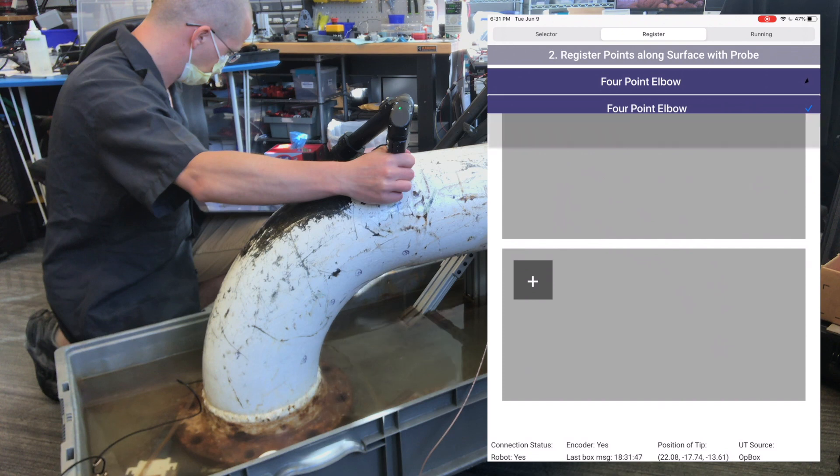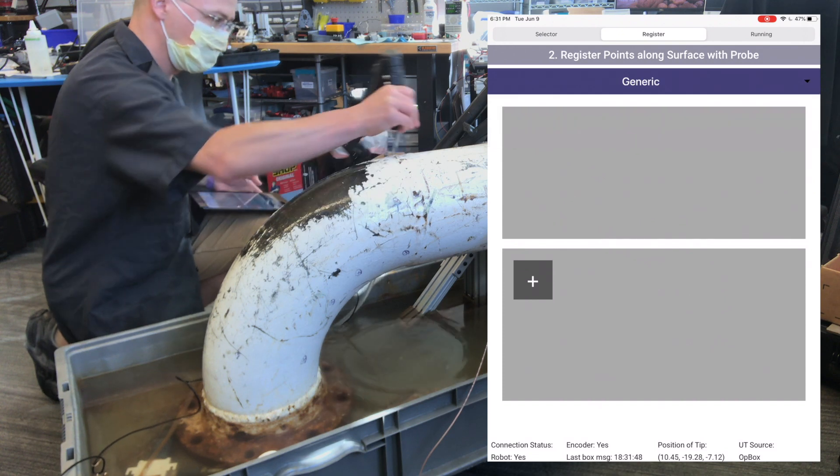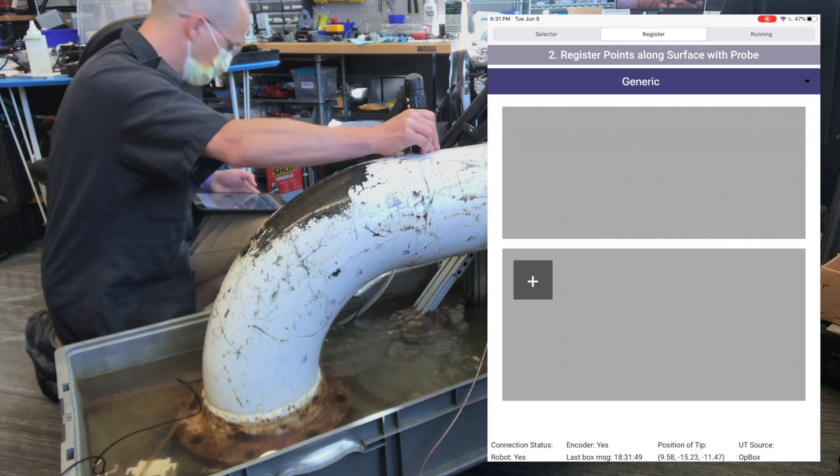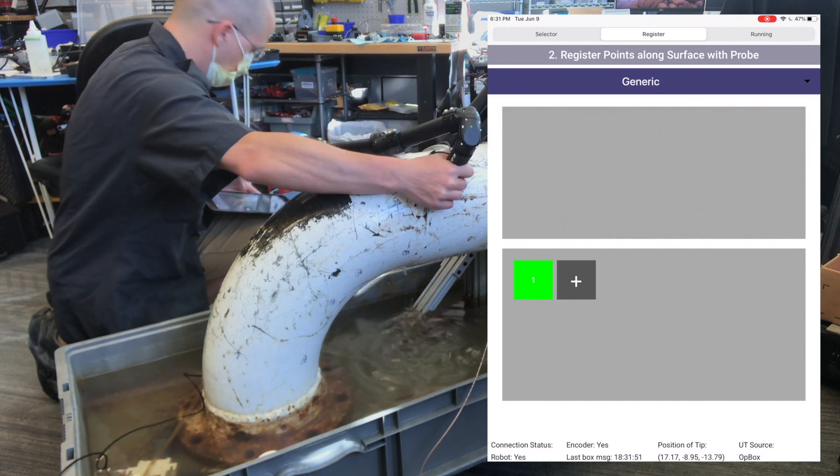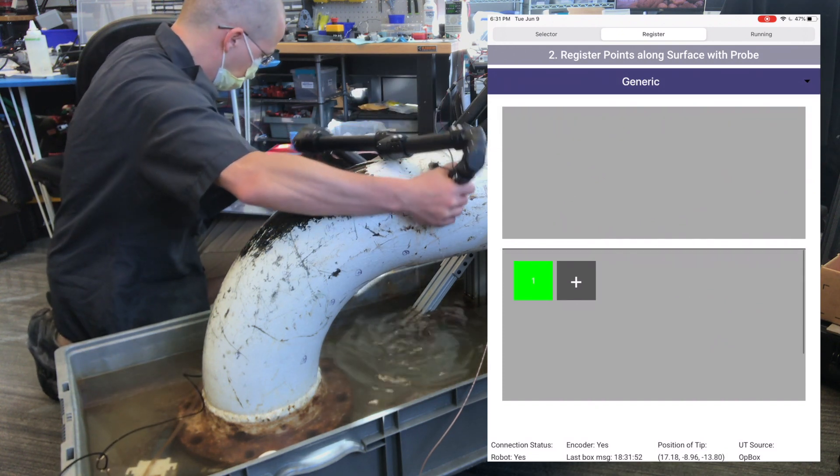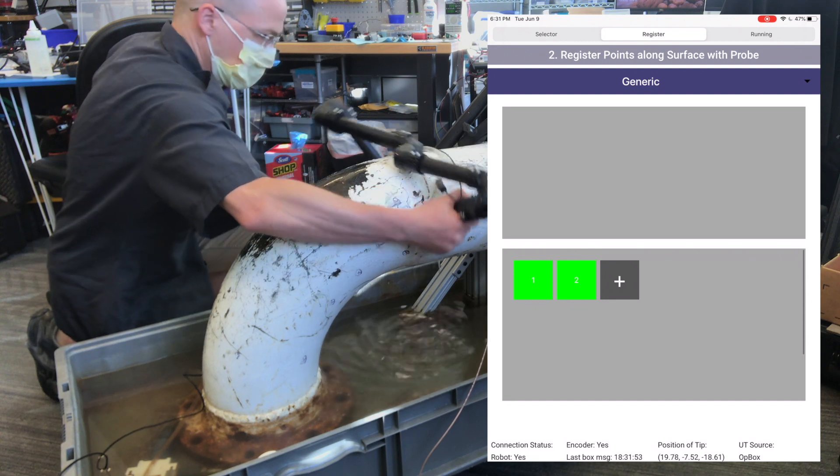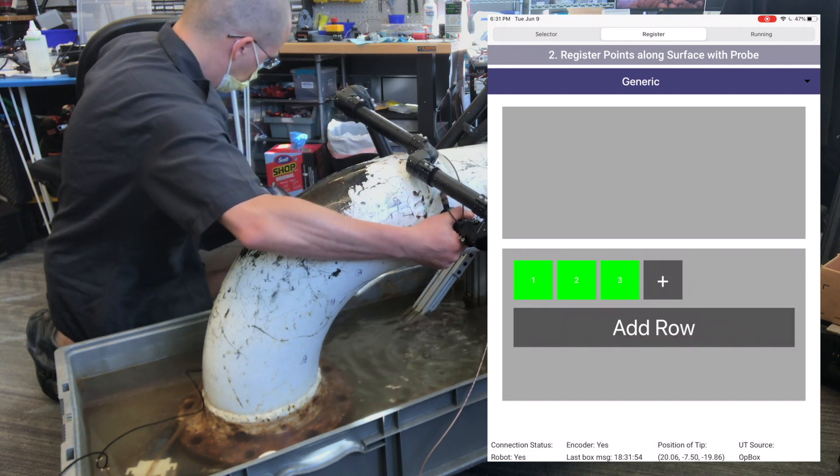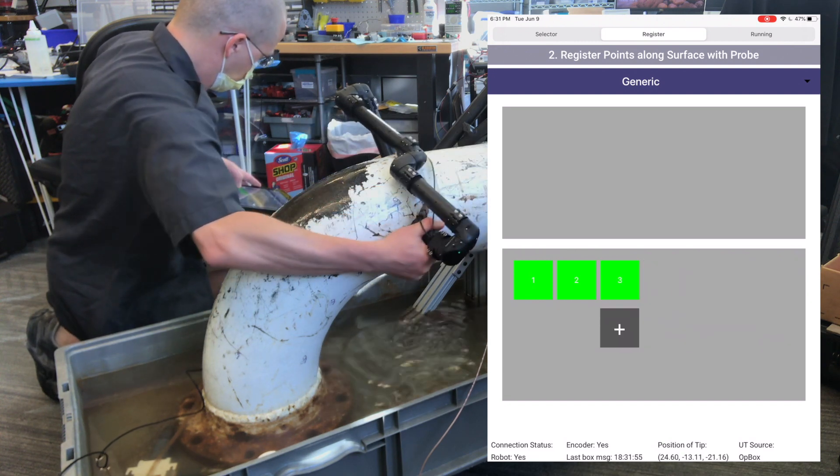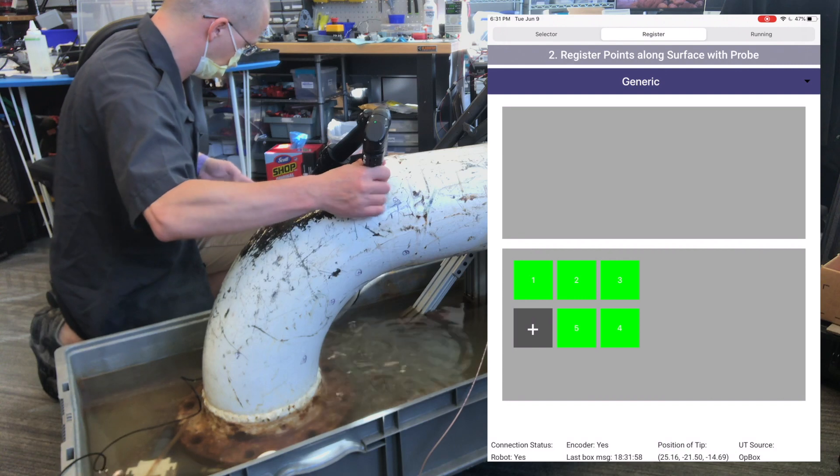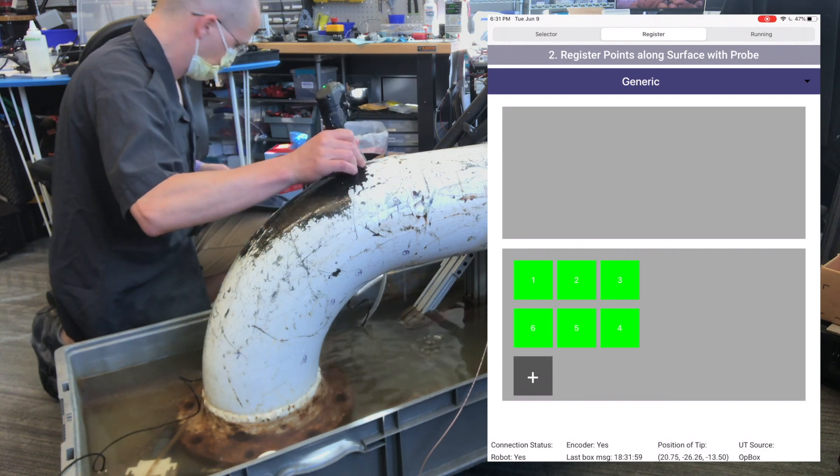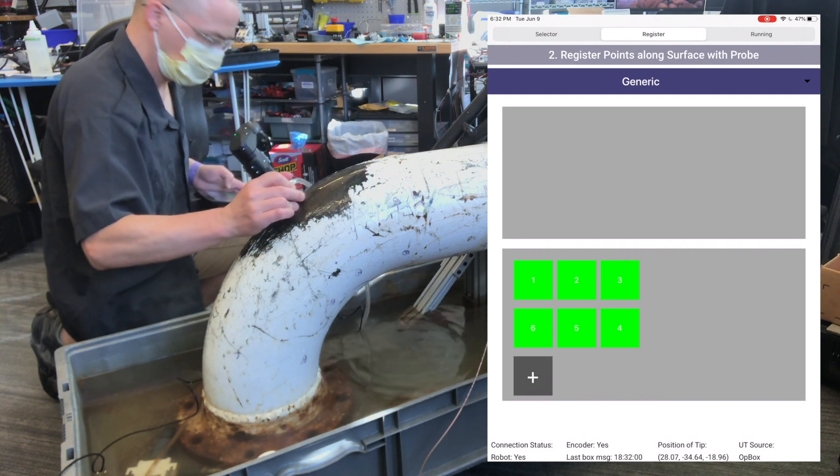MAPS is not just limited to pipe elbows, and can be used to inspect really any 3D surface by putting a loose grid of 2D points on top of it. You can think of this as putting a 2D map on the surface of the earth.